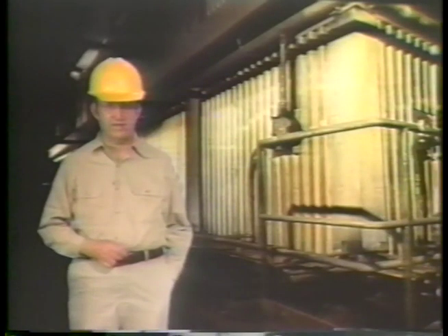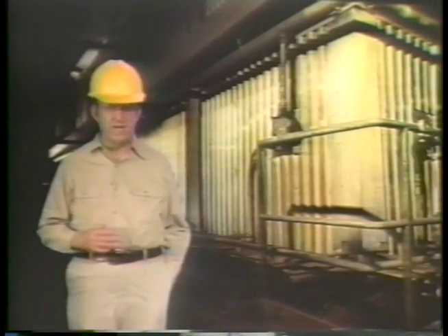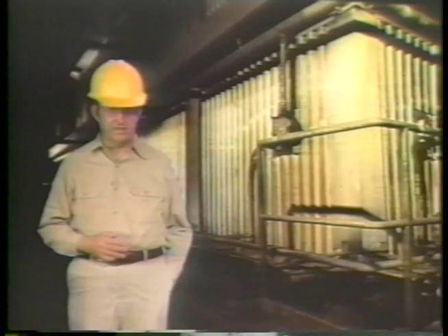The pressure in your boiler furnace will determine whether or not you have an induced draft fan. Some furnaces are pressurized, operating at pressures above atmospheric pressure, and do not have an induced draft fan. Other boilers are called balanced draft, and their furnaces operate at pressures slightly below atmospheric pressure. Balanced draft boilers have induced draft fans to maintain the furnace under a slightly negative pressure. For the most part, the flow path of air and gas through a boiler is the same regardless of whether it's pressurized or balanced draft. For our purposes, we'll use a balanced draft boiler to explain this flow path.